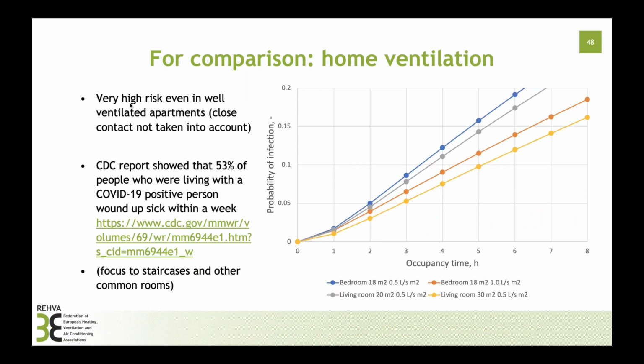And comparing to home ventilation, it's typically 0.5 air changes in homes, and these values will immediately be very high, showing that this calculation is very well in line with what is reported from other studies. One by US CDC reports that if somebody at home is infected, then 55% of family members will get the infection within 1 week. So it's very easy to get infected at home if somebody is infected. And home ventilation has no capacity, because 0.5 air changes per hour is 10 times less compared, for instance, with meeting rooms or classrooms.